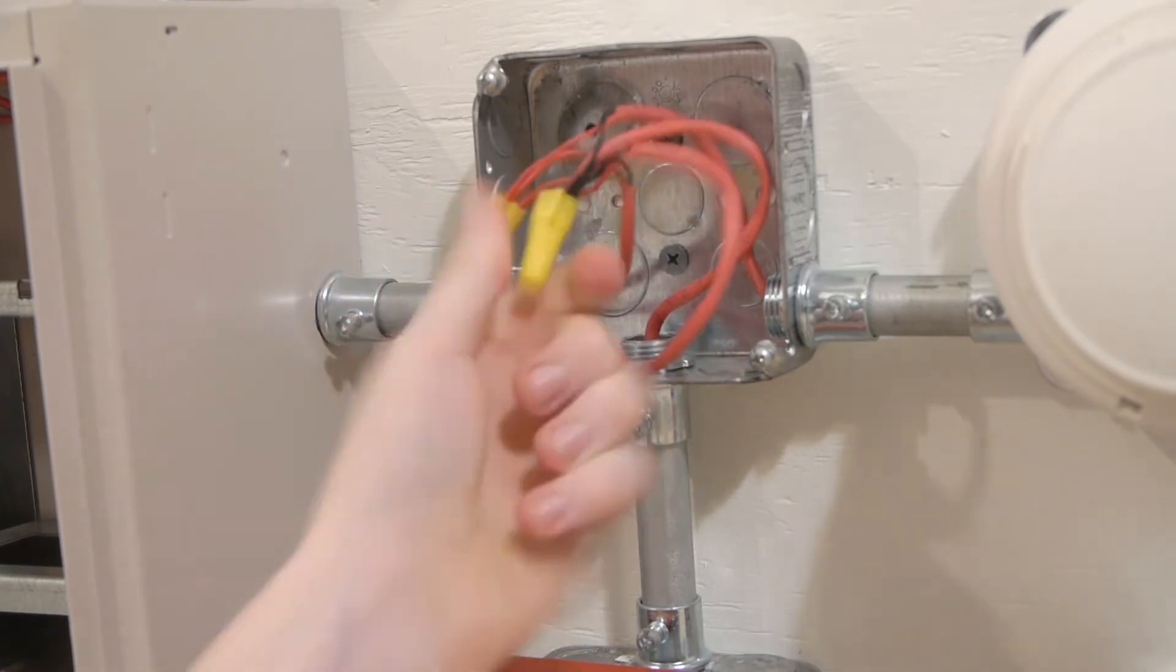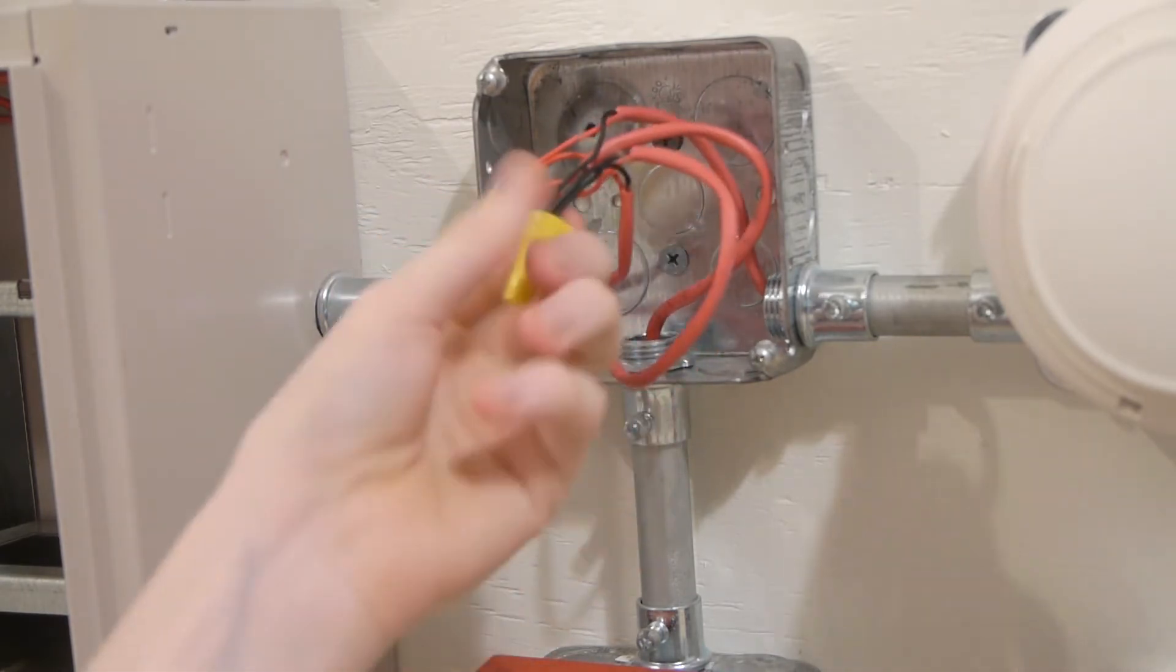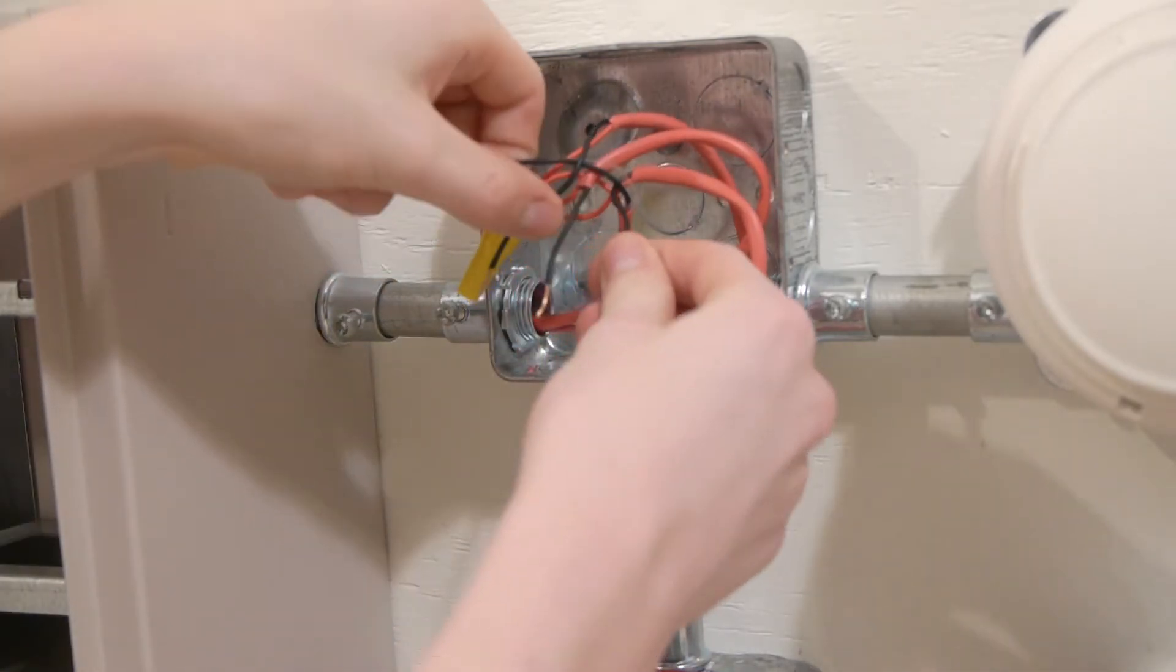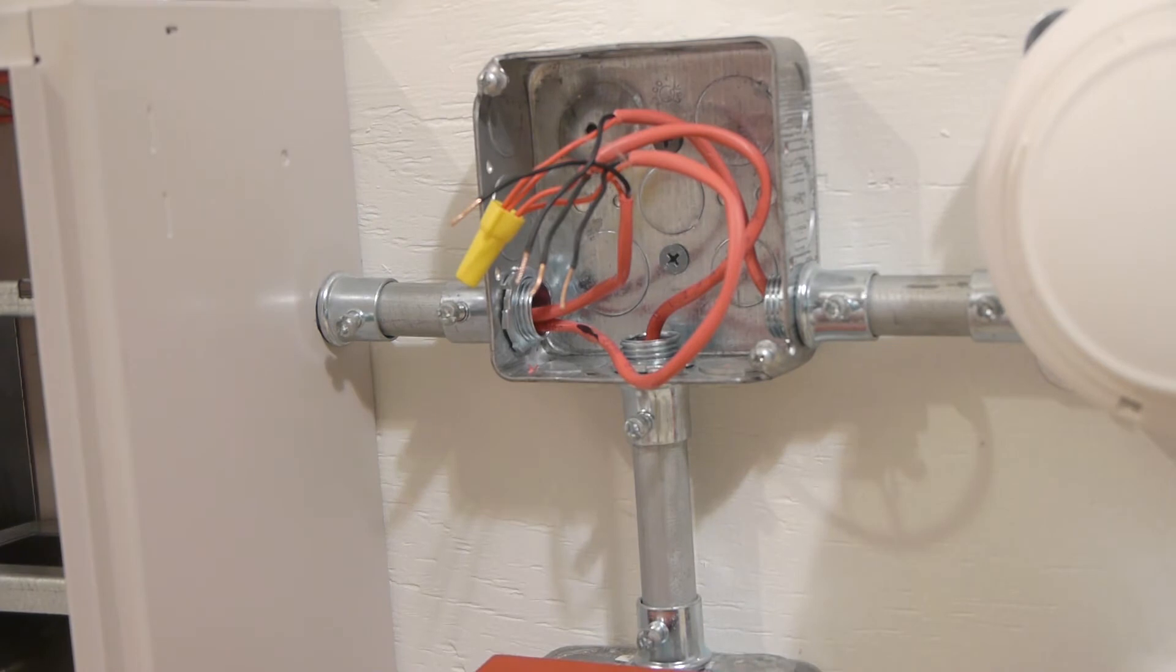I'm basically just going to unscrew this wire nut and separate each branch of the SLC circuit. You can hear that there can be some troubles popping up because all the devices are disconnected.